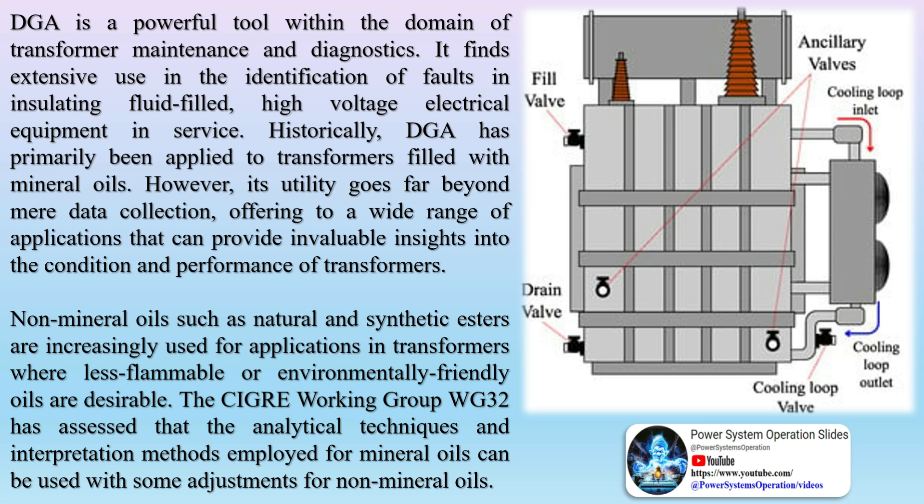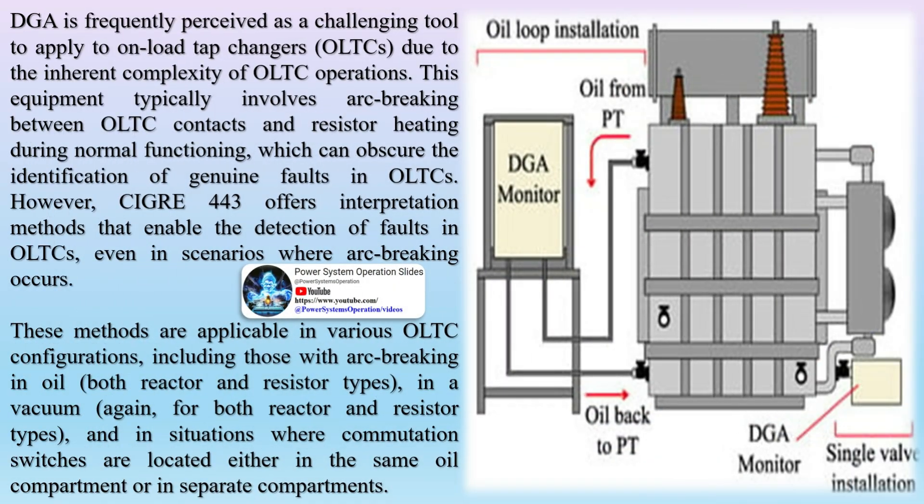DGA monitoring on power transformers: dissolved gas is a leading indicator of the health of a transformer. Dissolved Gas Analysis DGA helps determine the types of abnormal events that may be occurring within the main tank. It is an effective way to analyze partial discharge, arcing, excessive thermal conditions and more.